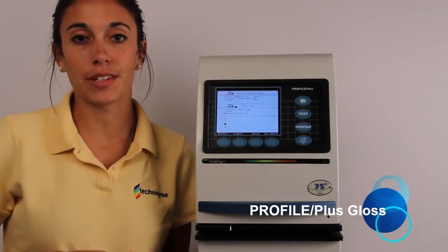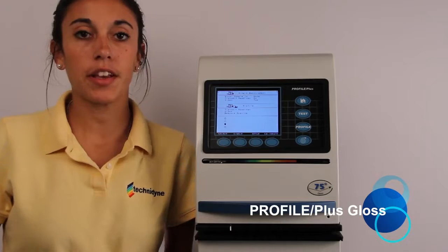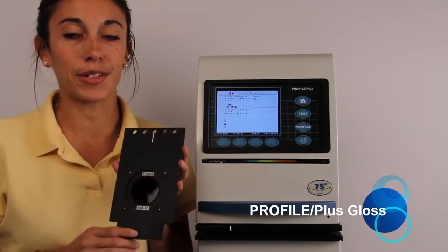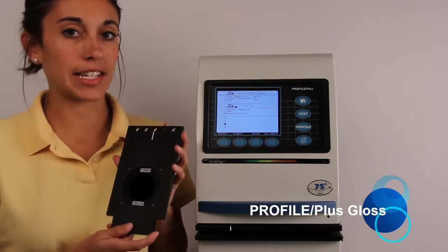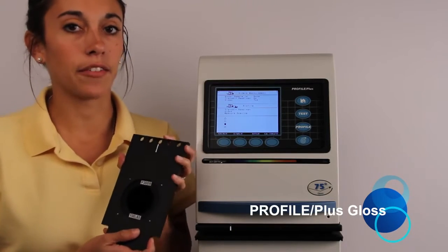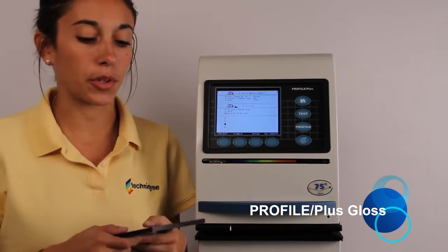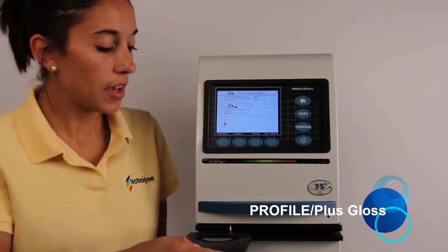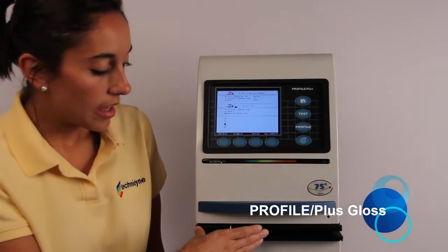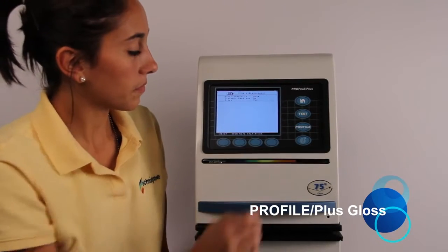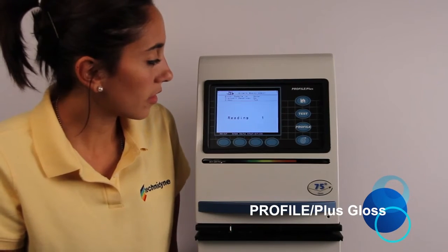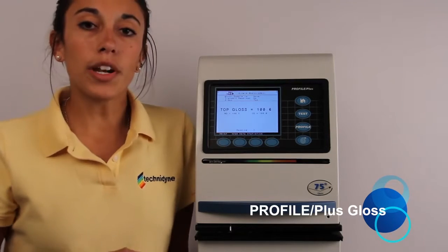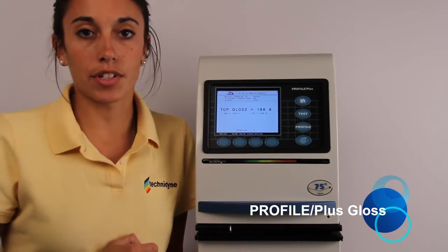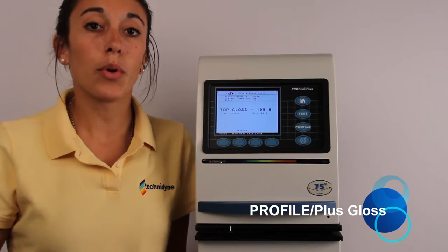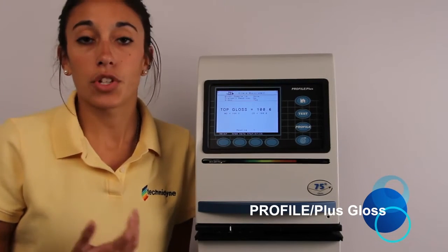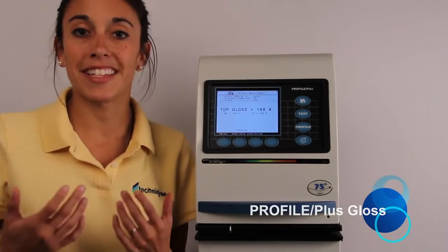Now that primary calibration is complete, we can verify calibration a couple different ways. First, we can use the cross-check reference tile you received with your instrument. It'll have its value already assigned to it. Ours is 100.65. Now your instrument should already be back at the home screen, so making sure that the white lines are matched up, you can go ahead and load your standard, and we'll press the test hard key. We want to check the MD and the CD numbers. As long as those are within plus or minus 0.5 of the assigned value of the standard, which in our case was 100.65, then that's exactly where they need to be.